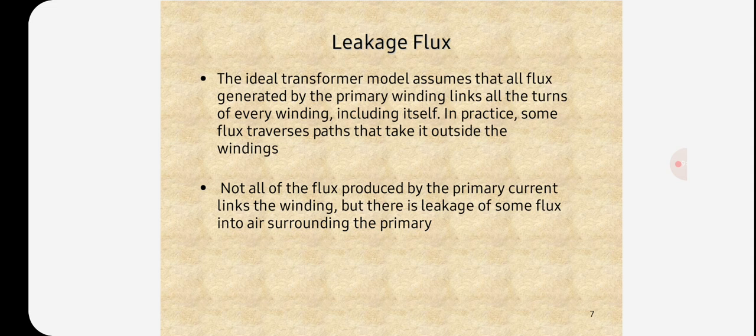At no load, the primary current is small and secondary current is 0. Hence, the primary and secondary ampere turns are small. Therefore, leakage fluxes are negligible. But when load is increased, both primary and secondary windings carry huge currents. These currents increase the corresponding ampere turns, which increases leakage fluxes.